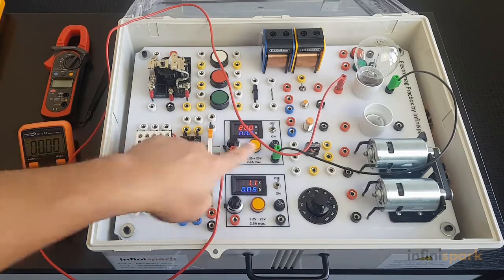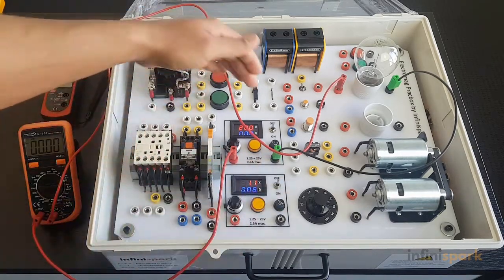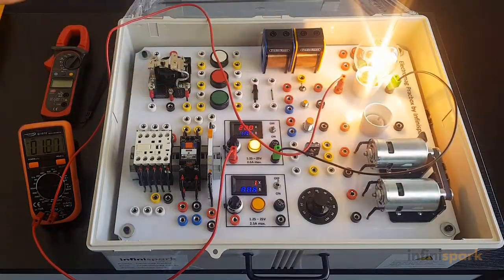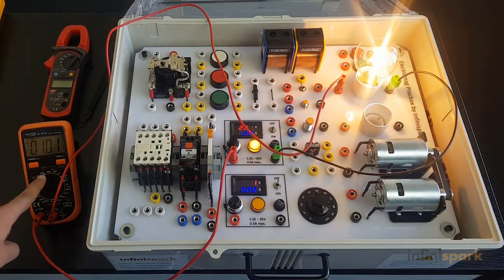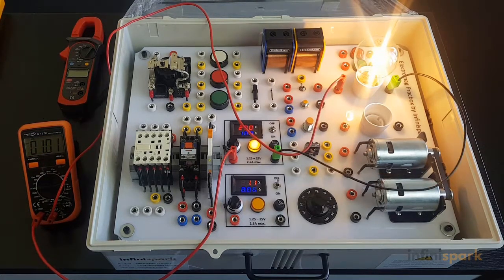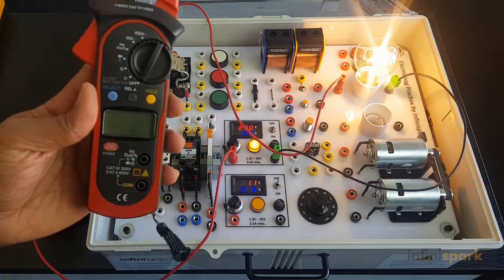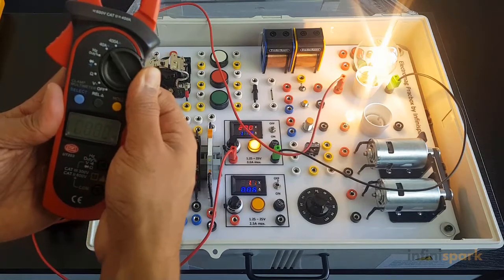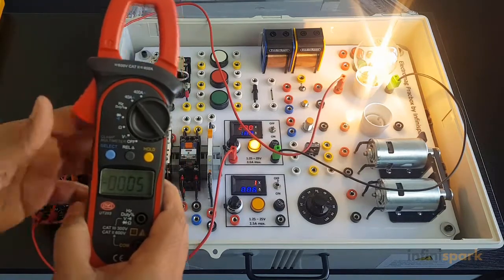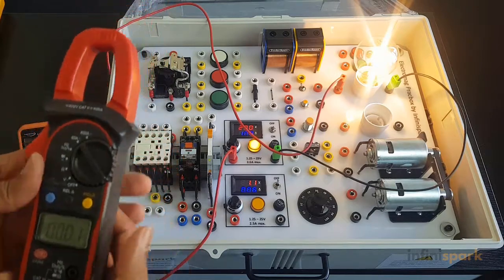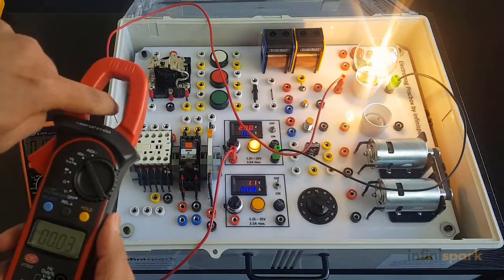Right now we have no current because the switch is off. Let's turn the switch on and see how much current we get. We can see that we're getting around 1.01 amp, so just about 1 amp of current. While we have the current going through this ammeter and the lamp is on, let's also use our clamp-on ammeter. This is our clamp-on ammeter, AC and DC both. If I go to my setting of 40 amps, since I already know the current will be roughly 1 amp, and force this wire to go through this loop here.